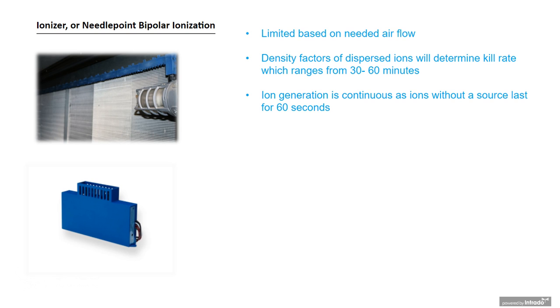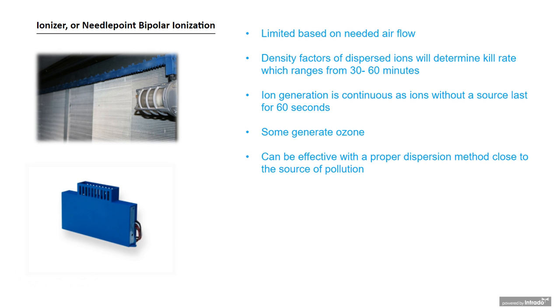They work if they're at the air handling units and you're looking to provide a solution within the HVAC system or deactivate the filters themselves. They do have value if you understand why you're implementing them and you know exactly what the needs of these ions are. They're not going to provide room level mitigation installed in the HVAC system. Also, some do generate ozone.